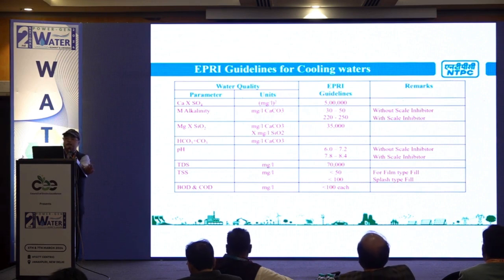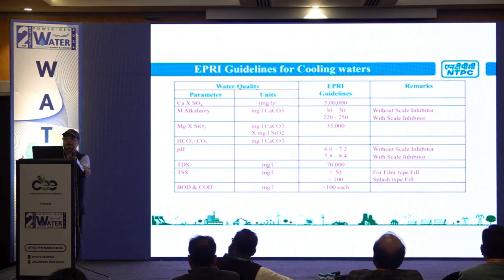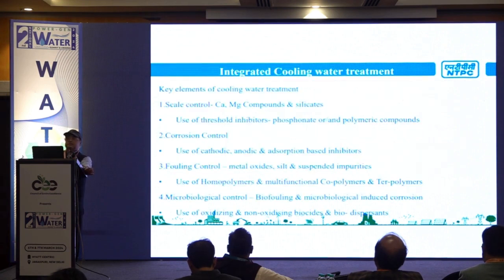So these are the parameters, or the limitations, of alkalinity, magnesium silicate, pH, TDS, BOD, COD - we have to control all these. In our system, magnesium silicate is around 5,000, and all parameters are well within these EPRI guideline limits.